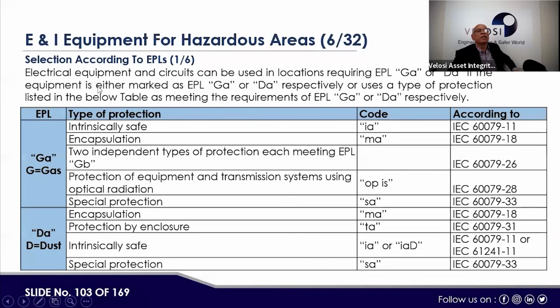Now, if we see the selection of EPL, on these slides, electrical equipment and circuits can be used in locations requiring EPL Ga or Da if the equipment is marked as EPL Ga or Da. This is what I explained. Here Ga means gas, Da is dust. We have intrinsically safe, encapsulation, 2 independent types of protection each meeting EPL Gb, protection of equipment and transmission system using optical radiation, and special protection. Similarly, the same properties are applicable on the dust side.